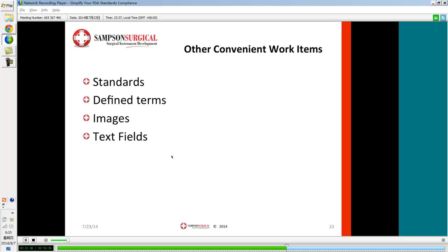Once you get the standard really vetted, on any project you wouldn't have to go through and re-understand what the 62304 standard means. In addition, you do it by revision. Say you go from 2007 to 2014: now you can evaluate the previous standard against the new one and identify specifically which standard requirements have changed. So you can do a differential on the standards, and also find out which products you've done over the past X number of years have been impacted by that standard, so you'd know where the standard is referenced. You could do a search cross-product and find out where standards are referenced.